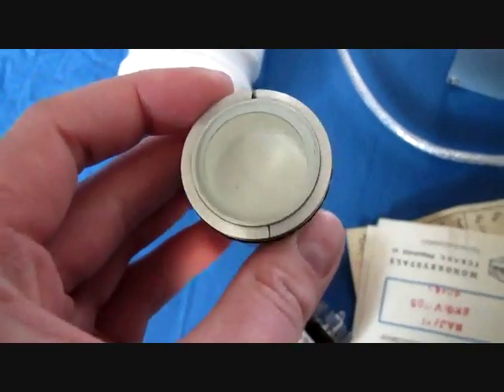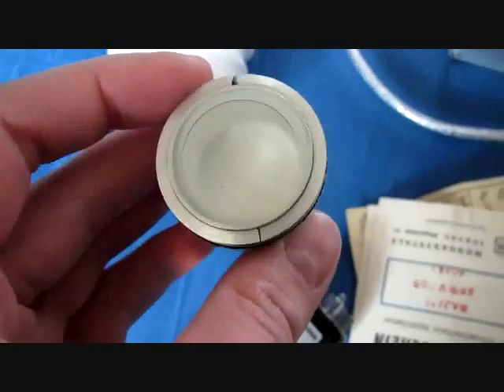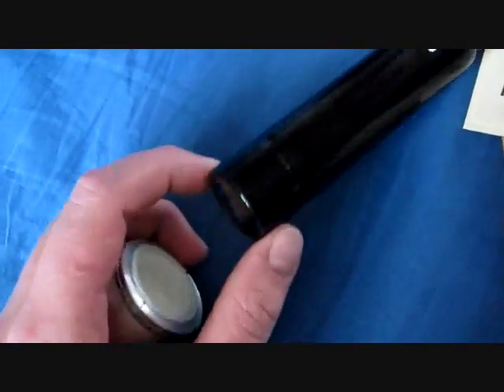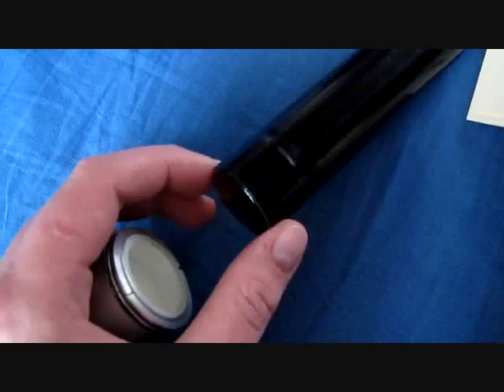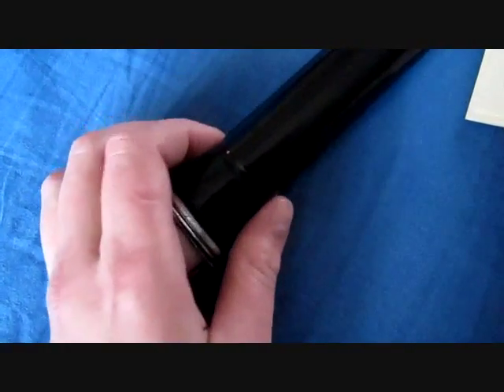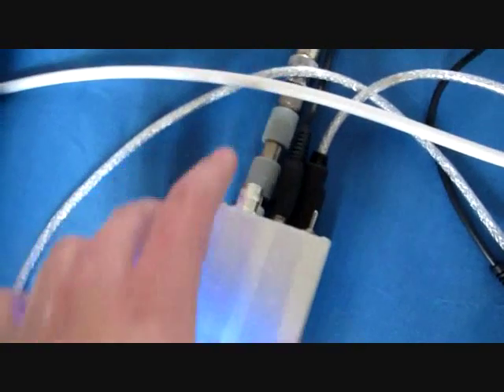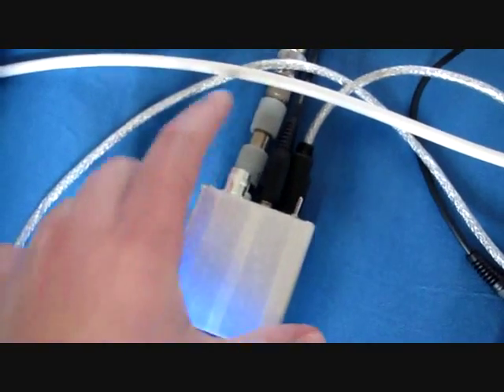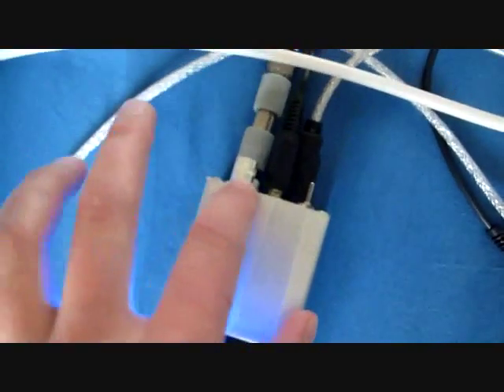You can see the see-through substance in here is the actual scintillation detector, sodium iodide, and it connects to a photomultiplier tube with some kind of light conducting fluid, which is a silicon-based gel, basically. So you just connect it like this, it goes into a base, and from the base there's either 1 or 2 lines, depending on the detector. There are versions of the Gamma Spectacular available for detectors with 1 line, which carry the high voltage and the pulse in one line, or with separate high voltage and pulse. I got the version that has both individually, so I can use any type of detector with it.